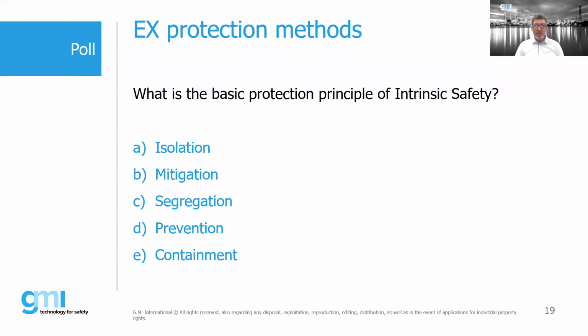What is the basic protection principle of IS? Of course, we're talking about barriers today, Zener versus isolators, so Bob gave us a very good introduction. And so it's biased toward intrinsic safety, of course. But what Bob has been telling is very true, the cost of installation for an IS barrier is less than that of an Ex d enclosure. Although today the wiring is still prevalently the same because people follow a different standard. They want an armored cable anyhow, but it's not a safety requirement. Okay, let's see. Some people are still voting. Let's give it a few more minutes.